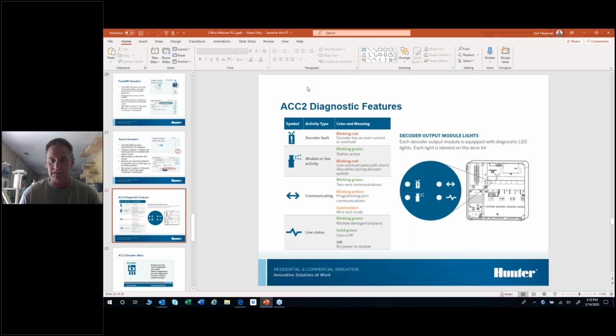The one in the upper right, the one that looks like two arrows, that's more of a communication type diagnostic tool. If it's blinking green, that means it's trying to communicate to decoders back and forth. If it's blinking amber, that means you've got programming port, like you were trying to stick a decoder in the two ports, and blinking amber means that you're now running it through that port for the time being. A solid amber means that you're in wire test mode. Now, the wire test mode we'll go into next week. That's how you can use your clamp on meter and go down the line and look for bad decoders, shorted decoders, problematic things that way.